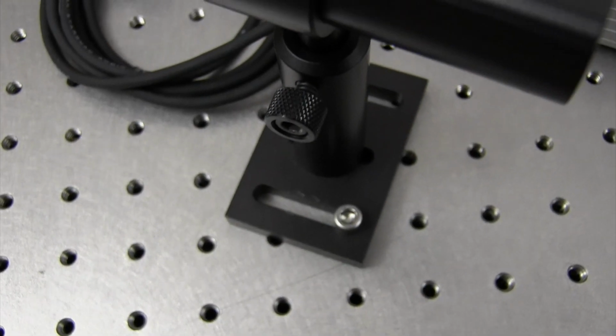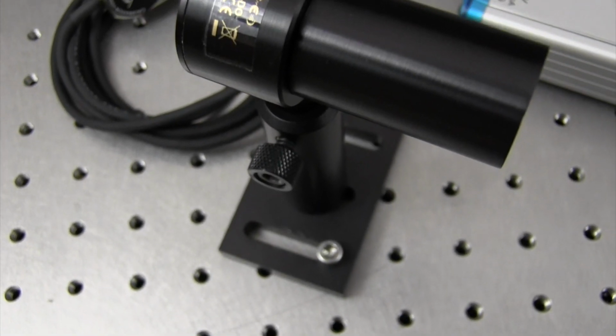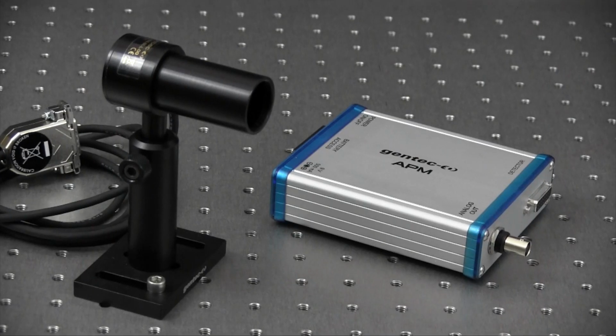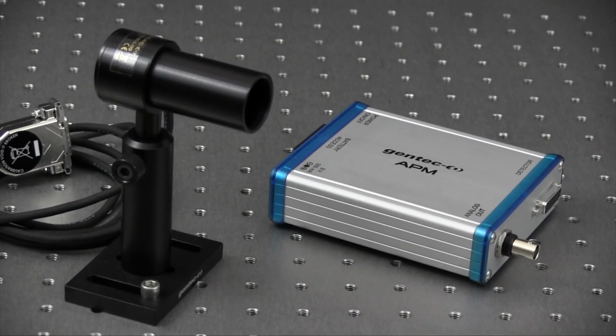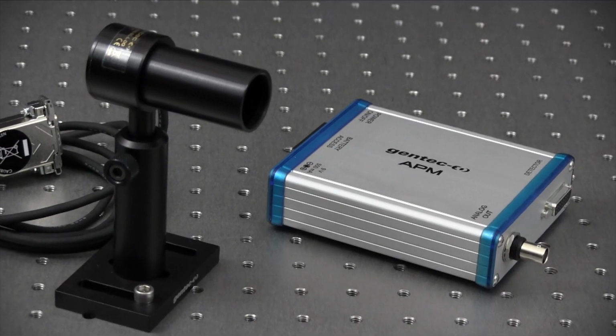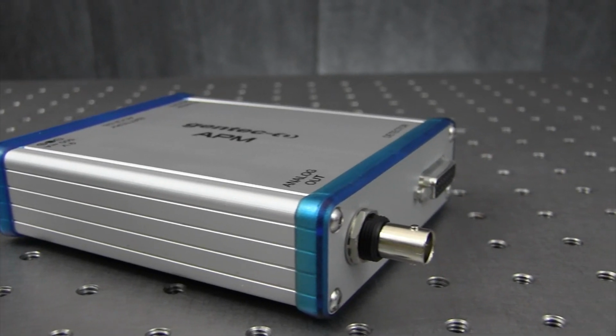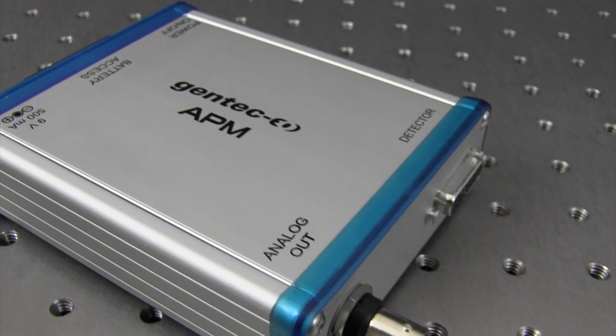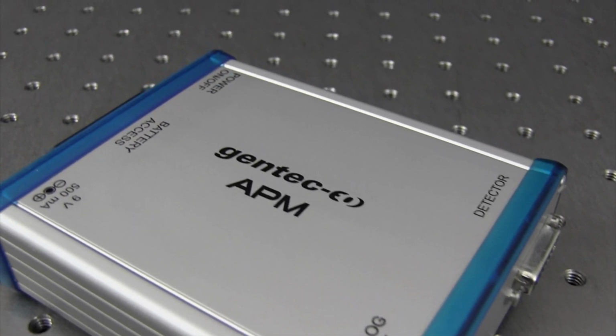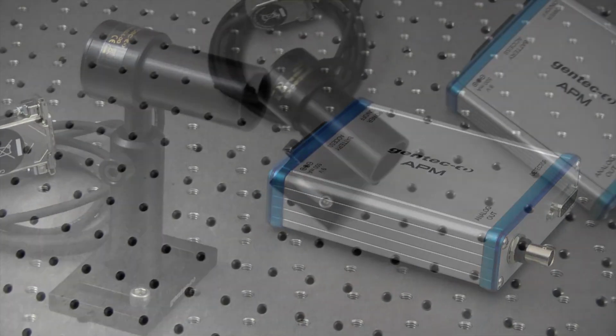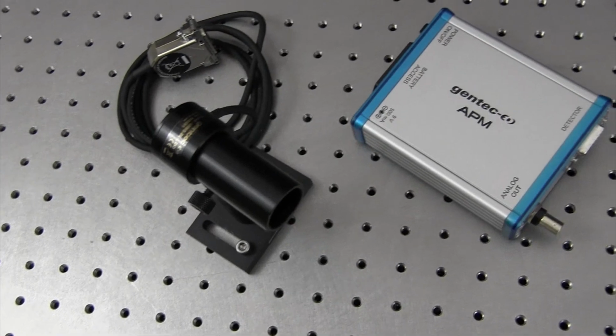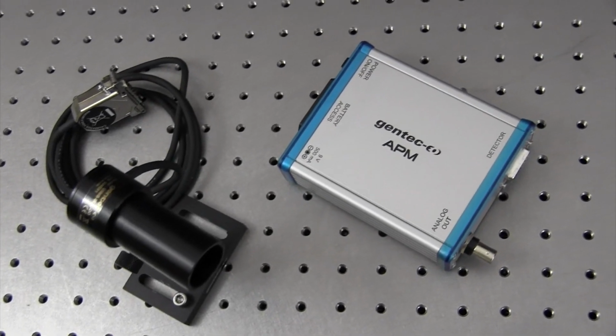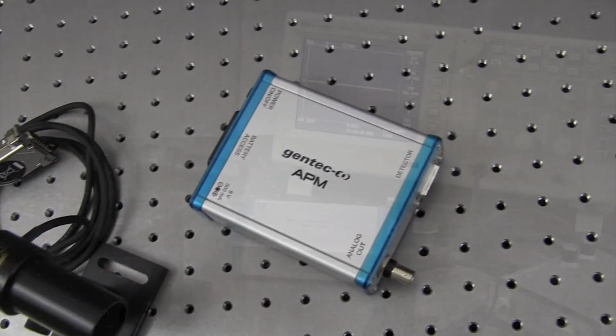First, let's talk about the UM9B detector. It's a very sensitive, high voltage output analog pyroelectric detector that is used with our APM analog power module. The APM powers the UM9B detector and provides the analog output. Notice that it includes a 2-inch light tube. This narrows the field of view and helps suppress EMI noise.